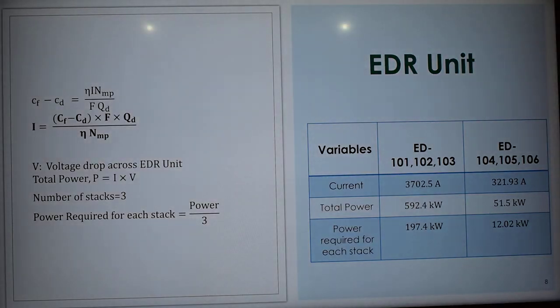calculated for EDR unit first, which requires current in order to run the unit. So we calculated current using the following equations, where we found I using the formula where CF represents feed concentration, CD represents the dilute concentration, into Faraday's constant, into the dilute flow rate.